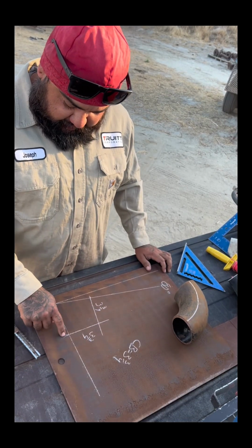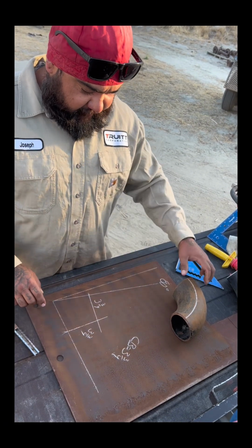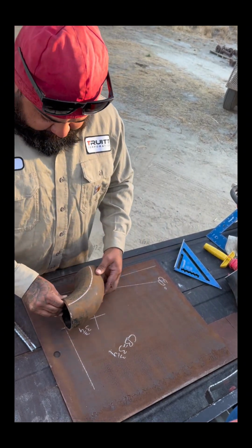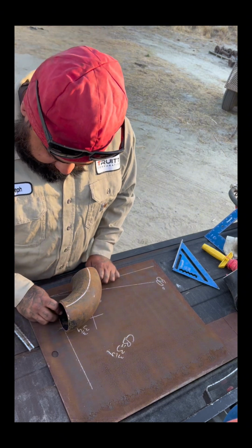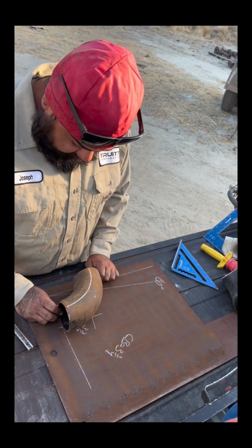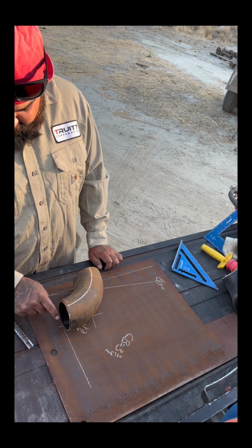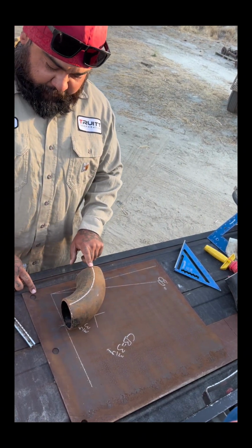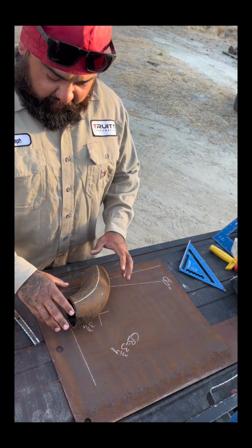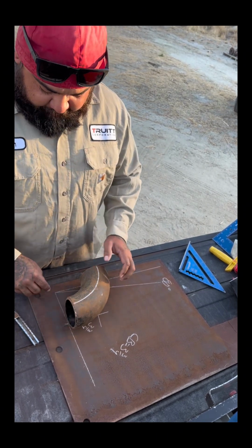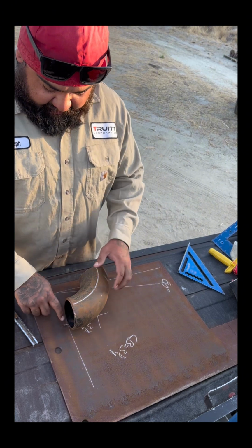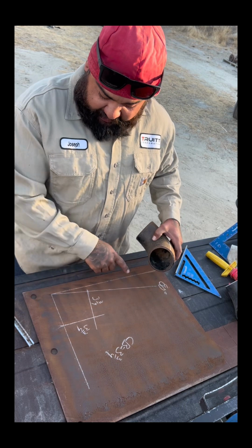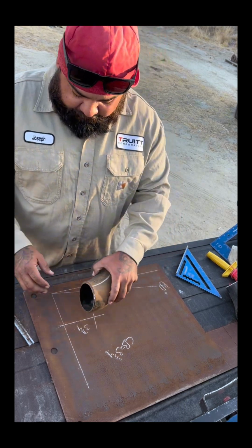So how I got this right here, the 4.5, it's because that's the cutback on a 3-inch 90, right? So this line just shows you the arc. So you line it up, okay? So this mark matches up here, and if you did the same thing on the lower end, it'd match up right here. Now you gotta keep the cutback on a regular 90 in mind, because that's how you're gonna get your center here, and that's also how you're gonna get your center on whatever degree you want, whether it's 80, 34, 20, whatever, okay?